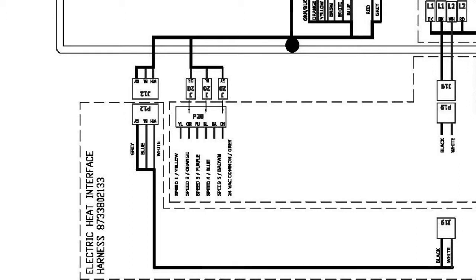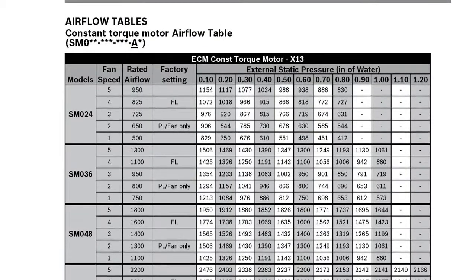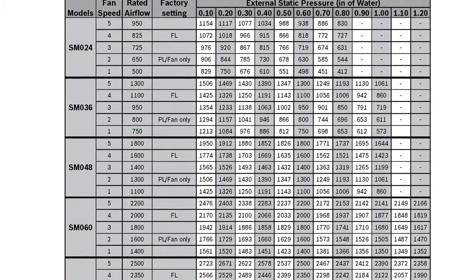From the factory, motor terminal number 2 is connected for part load and fan only operation, and number 4 is connected for full load operation. The CFM should be verified by comparing the measured external static pressure to the airflow tables located on page 58 of the installation and maintenance manual.